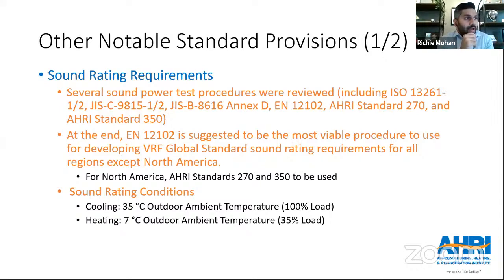So it's easy for a manufacturer, without a major testing burden, to conduct the sound test per one particular standard, and then if a different region requires, say, EN 12102, you can easily convert the tested data for the purpose of complying with that standard and its ratings. Sound is going to play an important role in this test procedure. For cooling rating conditions, we look at 100% load at 35 degrees Celsius outdoor ambient - usually the worst case scenario, when the system is loudest. For heating, we look at 7 degrees Celsius outdoor ambient at 35% load point.